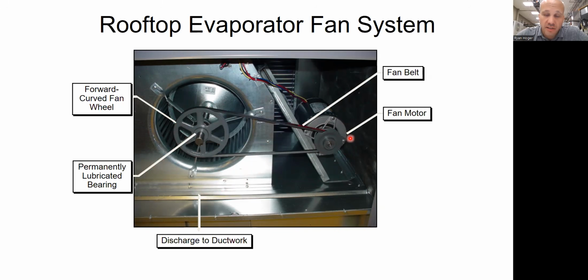When you put it in and install it, ideally, the person installing it would check how much airflow they're getting out of the system, compare it to what they wanted, and then change these to bigger or smaller pulleys to get what they wanted. Or sometimes they're adjustable, meaning that this gap can actually move in and out. If you need more detail on this, it's a side discussion, but I have all kinds of videos we've made on how to adjust belts and fan tension, belt tension on fans and pulleys and stuff like that. But that pulley can expand in and out, which changes the length of it and hence the capacity. You can also slide it up and down on this sled. There's all kinds of ways to adjust capacity on it.